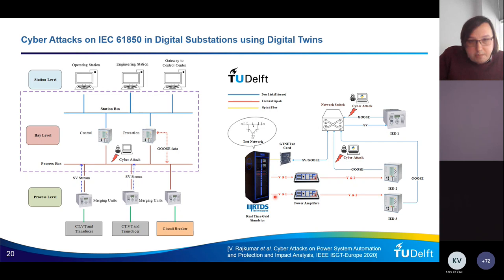And in our environments, we use the real-time digital simulator, the supercomputer, to simulate the power grid, a digital twin of the power grid in real time. And then we connect real devices, intelligent electronic devices like the merging units, protection and control, either with conventional hardwiring by using power amplifiers, or fully digital by using the 61850 sample values and GOOSE via a network switch. So we can connect the intelligent electronic devices.